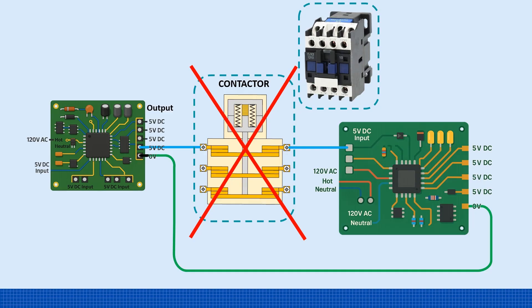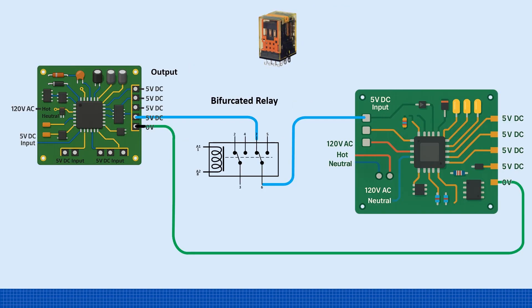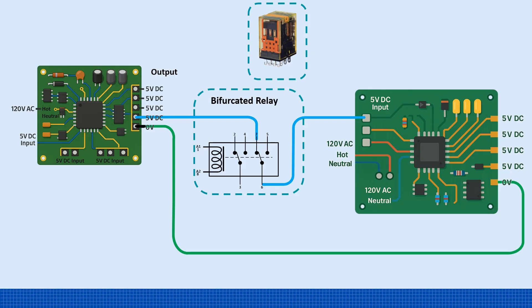The proper fix is to use a bifurcated relay. These are designed specifically for low-level signals. They're sealed units with dual-wiping contacts that make multiple contact points and scrape through any oxidation. This gives you a reliable, clean path, even at just a few volts.